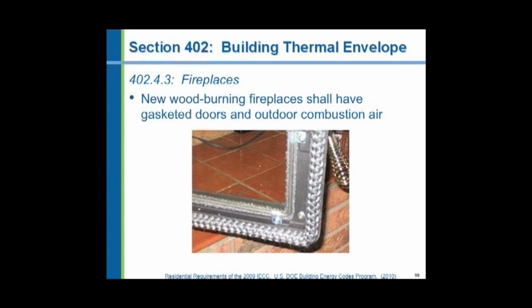When you run a fireplace, when you burn a fire, the combustion air has to come from somewhere. And in the standard historical construction, it comes from wherever it can. It comes from doors and windows and causes leakage and cold drafts in all the rooms of the house simply to provide combustion air for the fireplace. So they're saying put outdoor combustion air in there. That's easily done. Gasketing of the doors may be a more difficult situation. Custom doors manufactured for site-built masonry fireplaces, you may not be able to get gasketing on them. But the overall idea is to reduce infiltration, especially when the doors are closed, there's no fire, and the fireplace is cold.